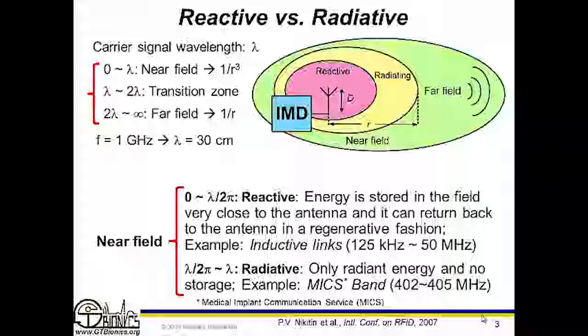You start affecting the tissue and the cells around that implantable device, and you might do more harm than good. With such a harsh and very strict constraint, we have to deliver this power, whatever amount that is needed. For example, in the case of retinal implants, something in the order of 100 milliwatts. How would you deliver 100 milliwatts during the operation of this device to this implanted item inside the body without raising the temperature at the surface of this device by 1 degree? You can imagine how efficient you have to be. The power dissipation should be extremely small across this small distance.